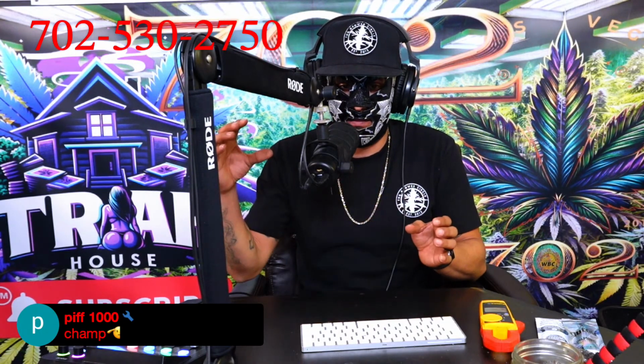What is hard is when you get there and everything's already wired, and you have to figure out which contactor is which and what controls what, especially when stuff isn't labeled. So now you really have to know what you're doing. And you can't just go in there testing contactors, because you don't know what they're doing. A lot of times a contactor could seem dead and you think you have a bad contactor, but the system could be purposely telling it to be off.